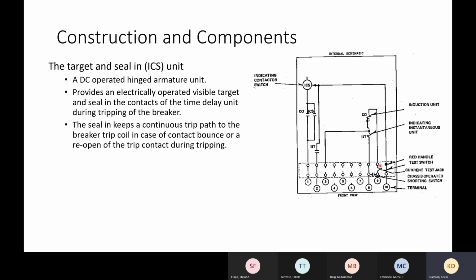The interesting thing of these cases is when you open the switch on the front, it automatically shorts these two together. Because one of the things you absolutely do not want to do is open circuit a CT while there's primary current flowing in it. If that happens, voltages will significantly increase really fast, and the insulation won't be able to sustain it, so you can actually draw an arc across it. So most relays, you may go out and see test switches underneath them, or there'll be some kind of test switch built in, and what that does, for the voltages and inputs and outputs, I can just open a switch and isolate the relay. Currents, almost universally that I've ever seen, have a special contact so that when you open it, it shorts on the other side of the block. And that's just for safety.